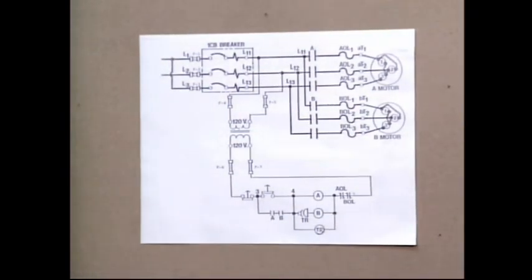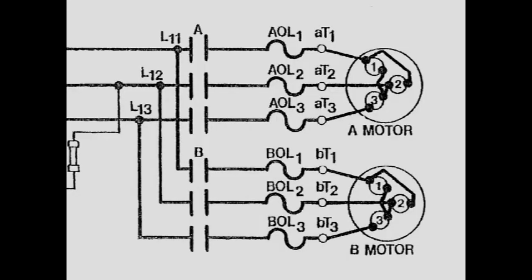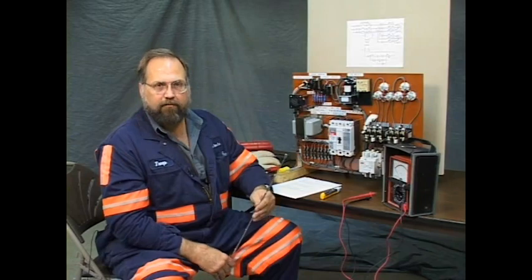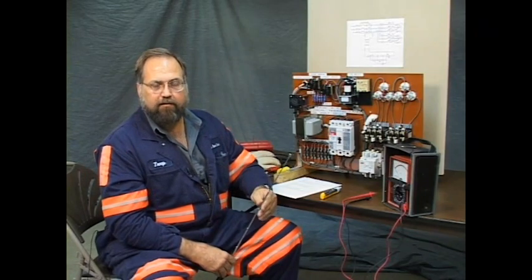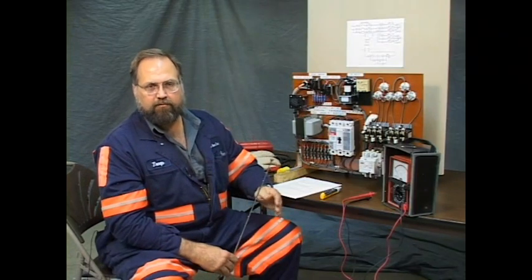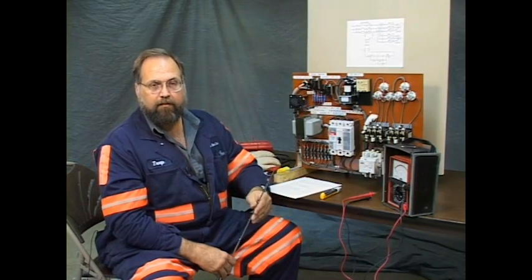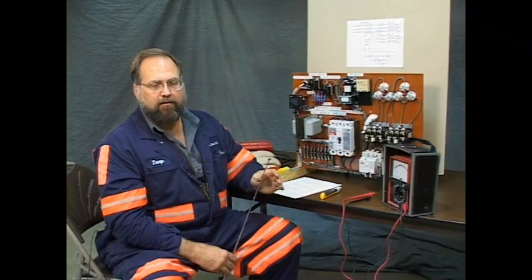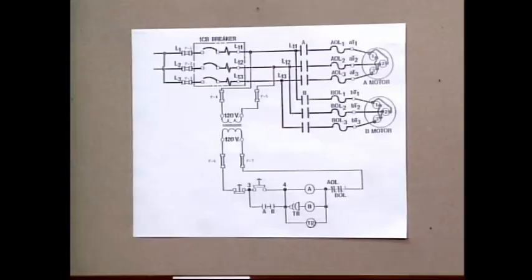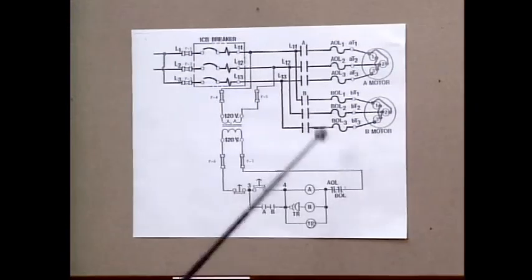The BOL has 2 elements. It has the actual current carrying element for the motor. The heater strips or the heater elements are in series with the motor and the contactor, and they're subject to motor currents. If the motor draws enough current to reach the set point or the rating of the thermal overload heater strip, it's a bimetallic strip, and the 2 metals involved, they respond differently to current. They'll bend, and when they bend, when they flex, they operate the BOL micro switch.